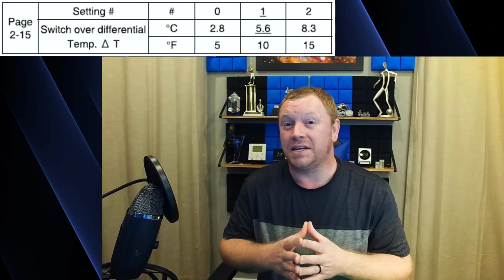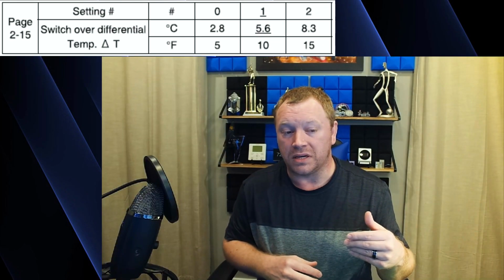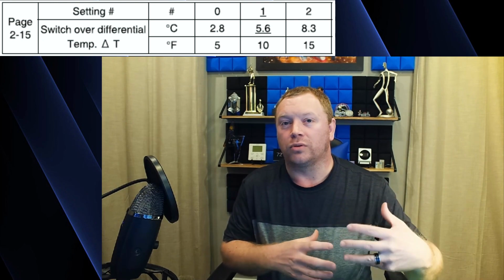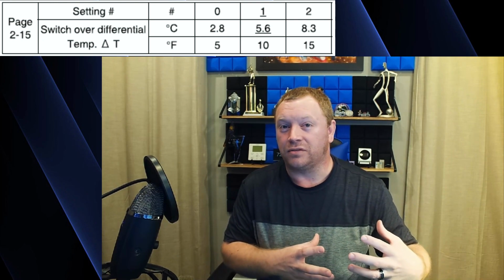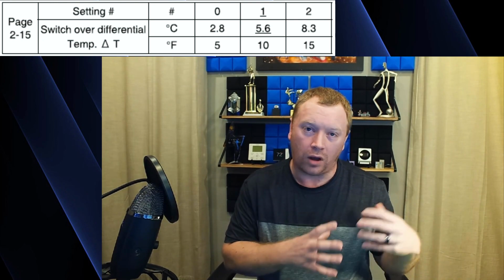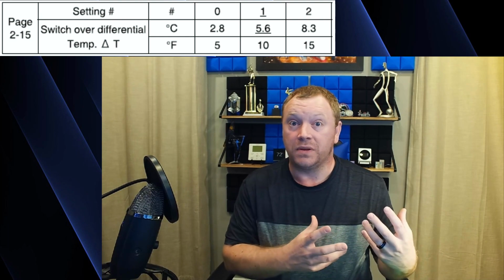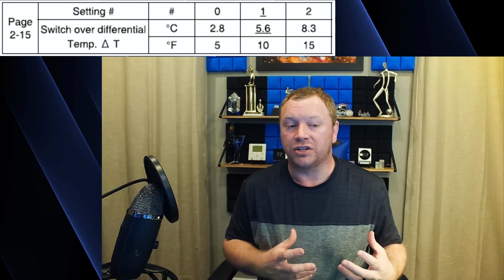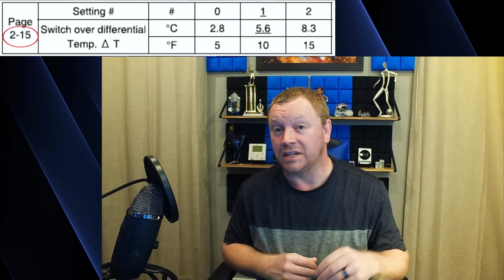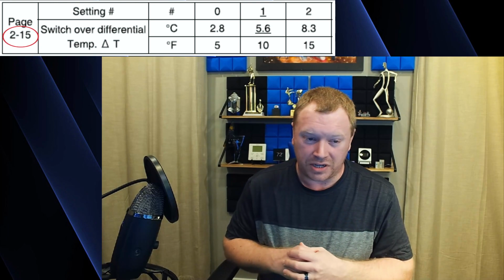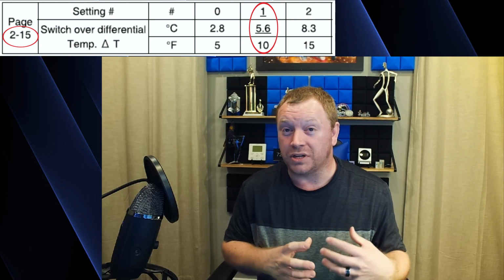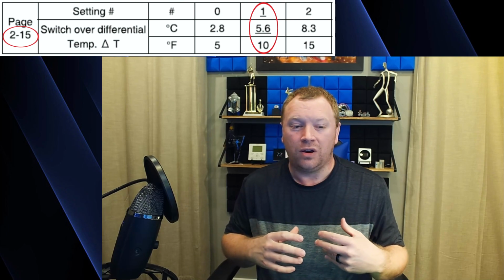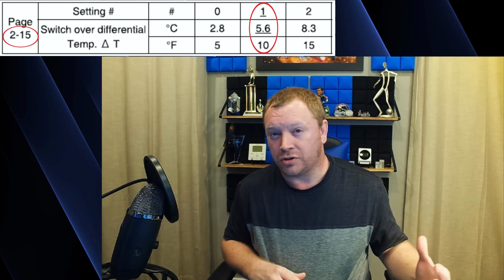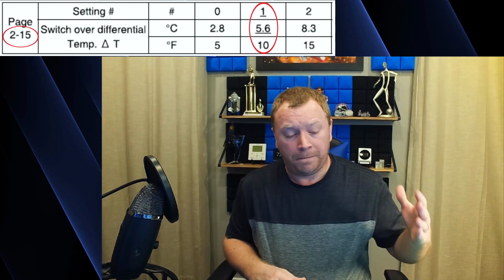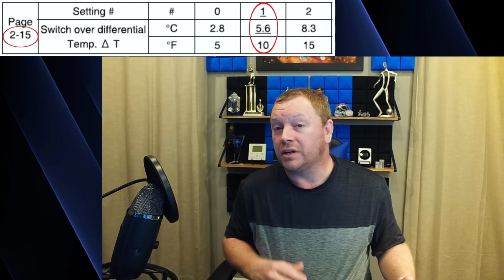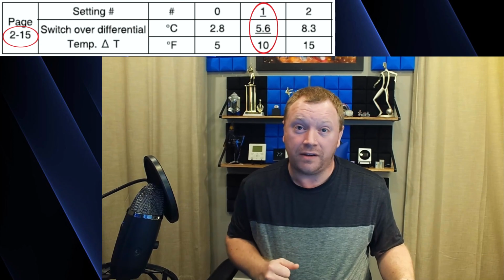The last setting we need to talk about is the number of outdoor degrees that have to recover before that lockout is disengaged. That is going to be mode 2, setting 15. And the default option is option 1, which is 10 degrees Fahrenheit. So if we leave everything default and the outdoor temperature drops to 15 degrees, then your gas is going to be running until the outdoor temperature is 25 degrees.